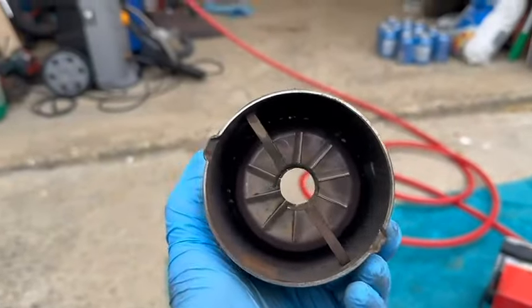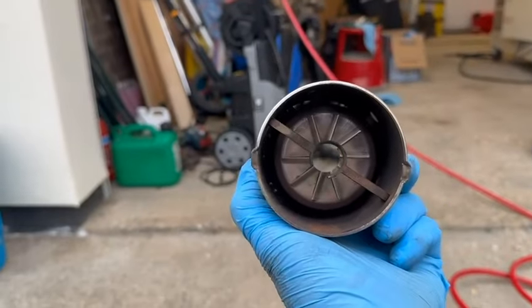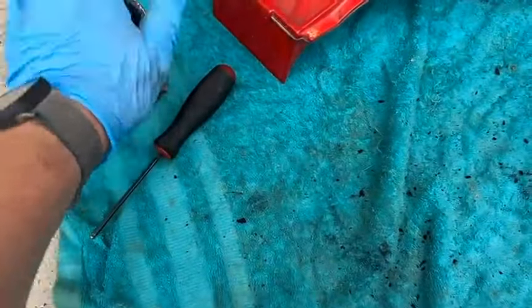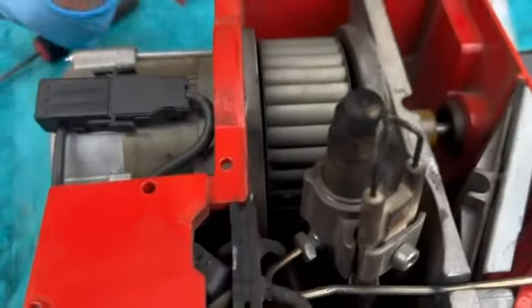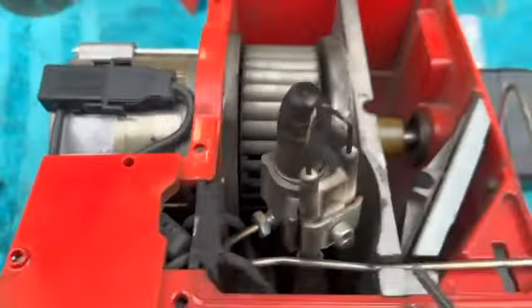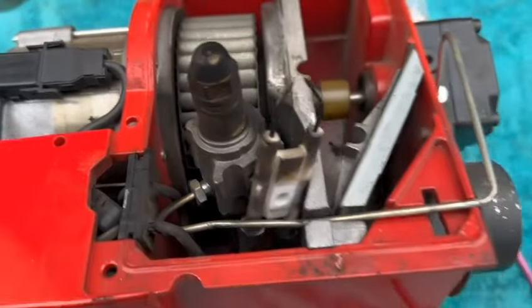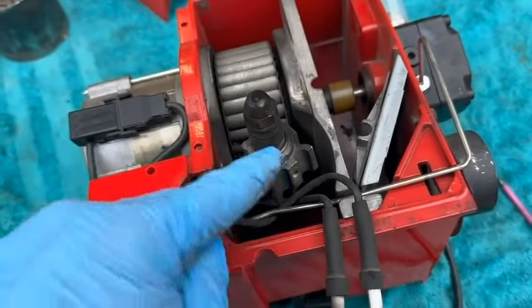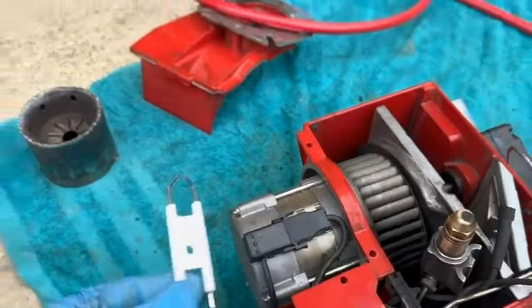It's done — nice and smooth all the way around, nice and flat across the top which is important. It's smooth inside, which is really important. The top was quite rotten in one area but I've managed to sort that out. I've also lined up the nozzle aperture in the back perfectly — that's absolutely spot on. The blast tube is done, a bit hot still but I'm happy with it — that'll get me out of trouble.